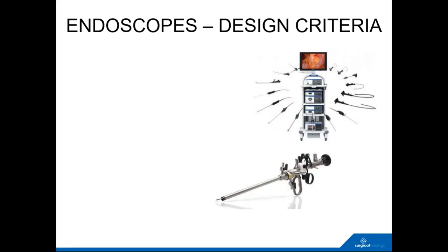So what are the design criteria for any endoscope designer, any endoscope company? The first is obviously the overall size, the outer diameter of the instrument. How big is the hole that you can actually go into? Obviously, the bigger the hole, the better you can use, better optics, more light, more channels for therapy, etc. And I mentioned, is it diagnostic or is it therapeutic? If it's diagnostic, you're really just interested in looking at it. But obviously, when you're there, if you can do some therapy or do something about whatever you see, that's a far better one-stop for the patient.